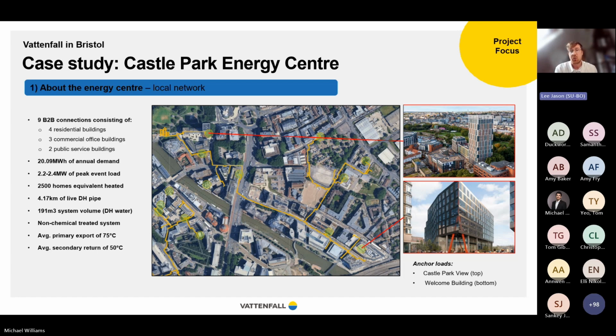The network has 9 connections - 4 residential, 3 commercial buildings, and 2 public service - giving good variation in demand profile. That leaves us with 20.09 megawatt hours of annual demand, a peak right now of around 2.2 to 2.4 megawatts during winter peak events, equivalent to 2,500 homes being heated, and 4.17 kilometers of pipework.